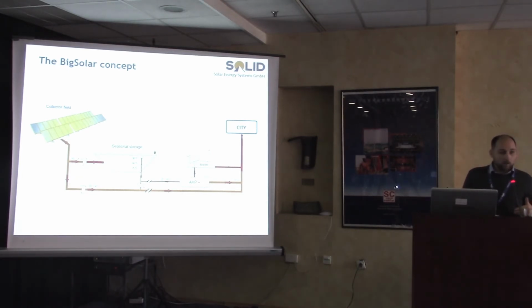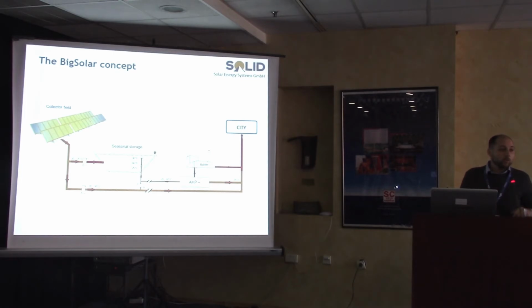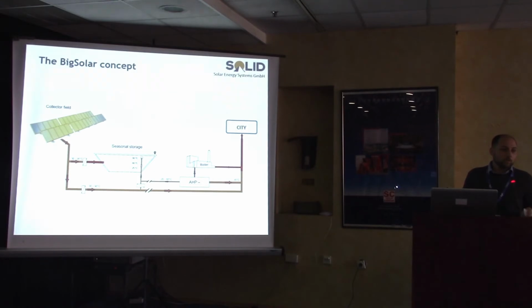The seasonal storage either also directly feeds into the grid or via the heat pump. When the seasonal storage is partly empty, the heat pump is a key element because it can lower the temperature within the storage to the return temperature of the district heating grid, which is also in favor of solar heat. So lower solar heat can already be fed into the storage. The storage could be emptied from 90 degrees Celsius down to 15 degrees Celsius. Without using a heat pump, you're always limited to the return temperature of the district heating grid.